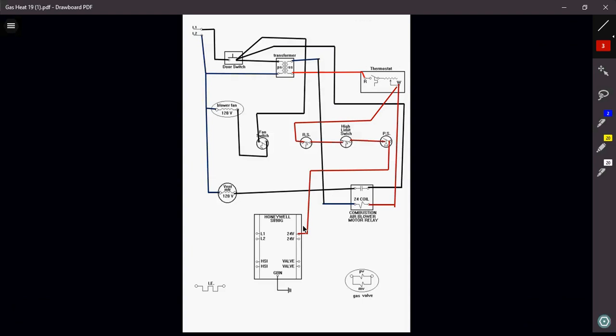Okay? Because remember, when it comes to combustion and ignition, you have your combustion triangle. You got to have three things in order for something to light. You got to have air, fuel, and spark, or air, fuel, and heat. If I take away any one of those three, I'm not going to have ignition. So if I de-energize my gas valve in the event of a safety problem, I just took away one of those three in that ignition triangle. I took away the fuel source. It's not going to do anything. It's not going to light.